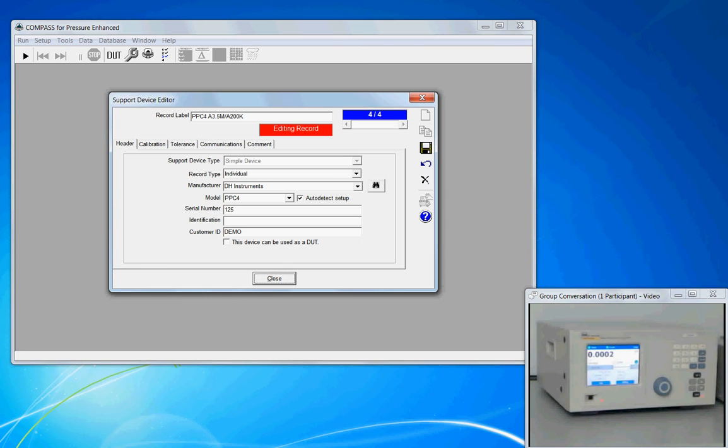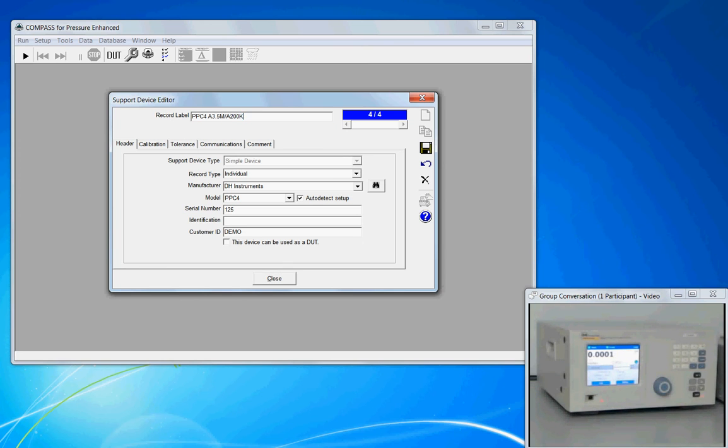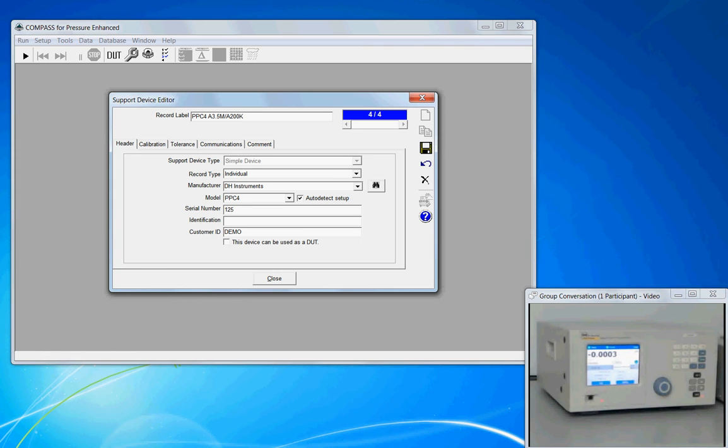We start by giving it a record label. This is just a text field. You put something in here that is descriptive to you so that you can easily identify the instrument when you start a calibration.